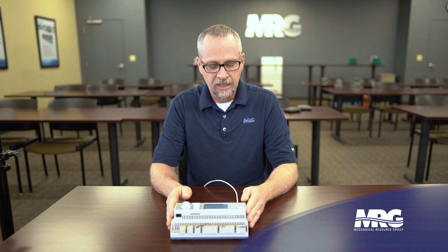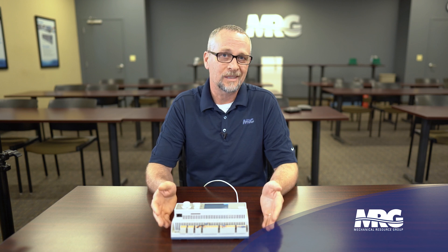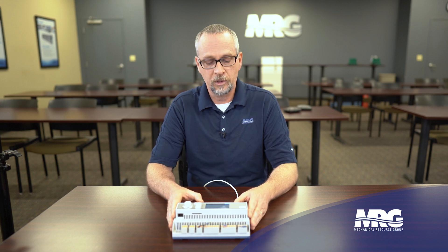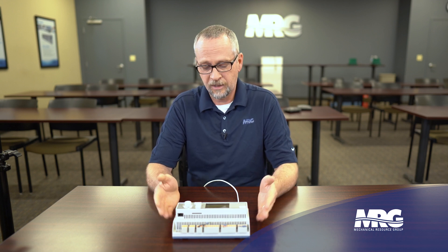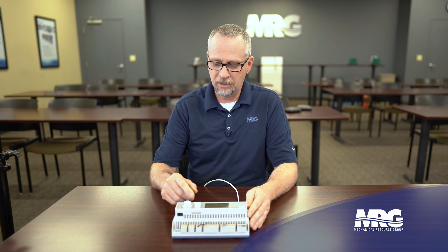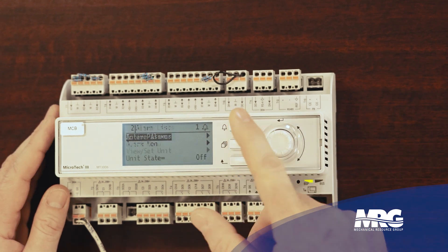One thing to note: if you ever hook power to the wrong source on this, you can blow a small fuse inside the controller that's kind of non-repairable. So just be careful, take care of it and it'll take care of you. Really solid controller, great product. We're going to do some more videos on some older versions of MicroTech that are still out there on some gear. For this particular video, just wanted to give a nice overview — only four buttons. This one does enter and scrolls, this takes you back one page, this takes you home, and this gets your alarm menu.